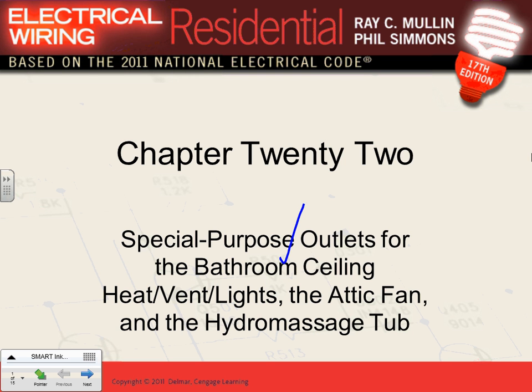One 20 amp circuit feeding at least one GFCI receptacle within 3 feet of the sink. Can I have thumbs up there? That's a requirement. Okay, now that's just the bathroom. How about the bathroom receptacle? How about the bathroom light? Two options for the bathroom light. You can feed the bathroom light directly from that 20 amp circuit, and all the wiring is going to be number what? 12 now, right? Going to the switches, and that's okay, check done.